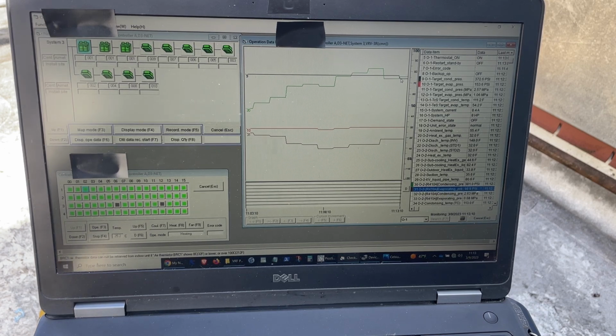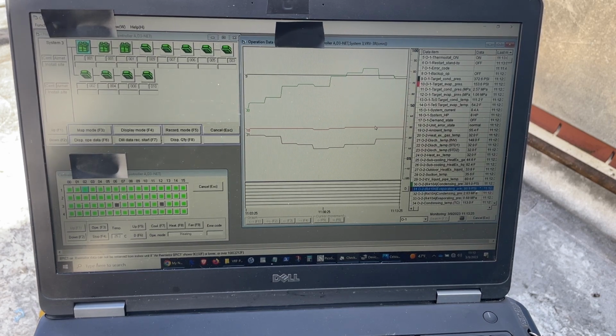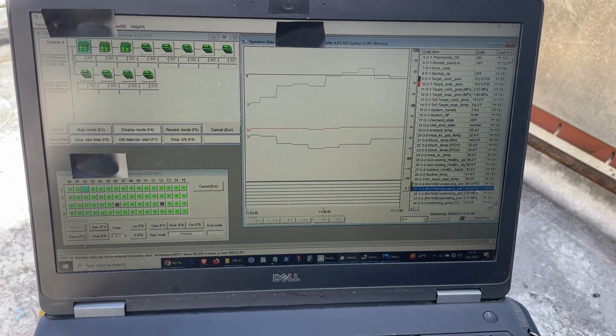There's some caveats in there, and again you have to be careful not to overanalyze what you're looking at. But these things are pretty good about controlling pressures, and that's what makes them difficult to diagnose refrigerant wise. You really can't look at these pressures. They're so good at controlling pressures that they can control them pretty well even missing a lot of charge. I've seen that quite a few times. So there are other things you need to look at to determine the refrigerant charge. But this one I know is correct because we weighed it in according to the submittal.